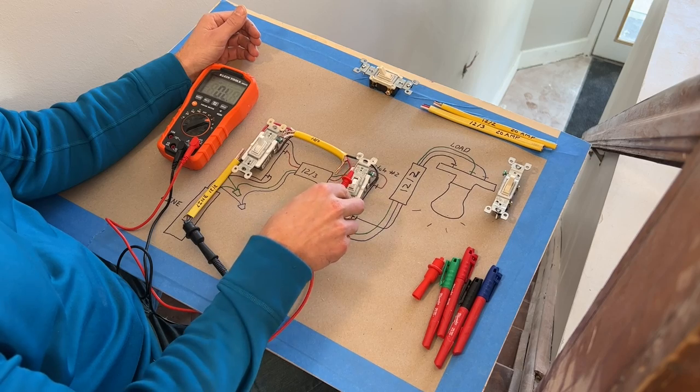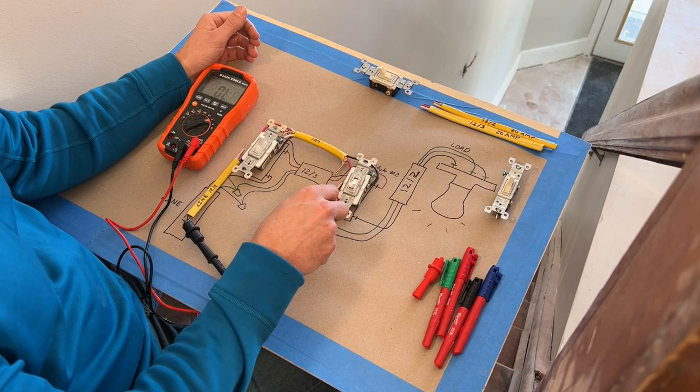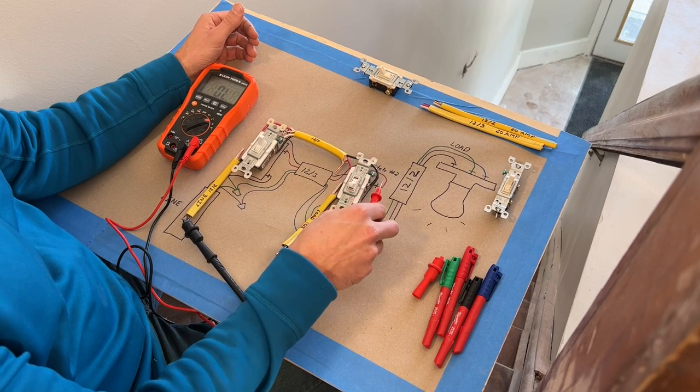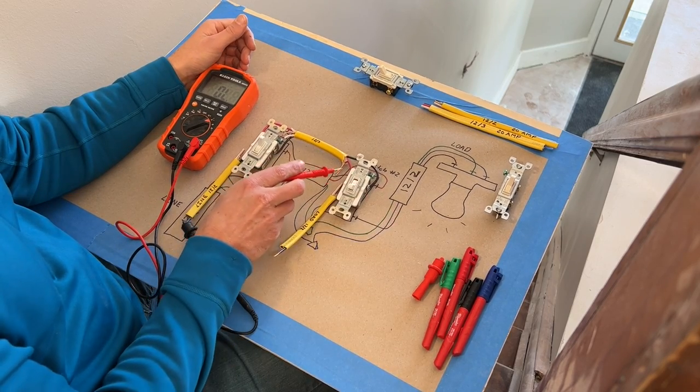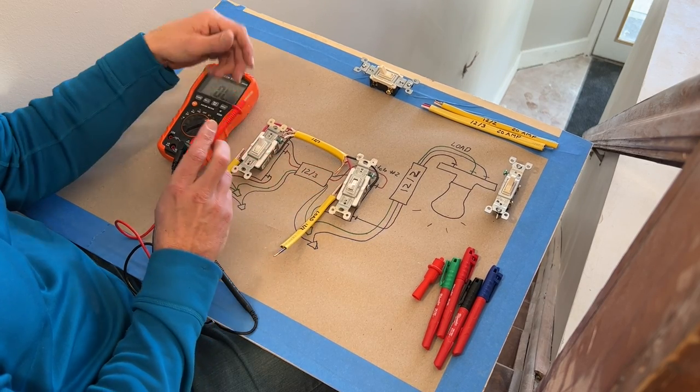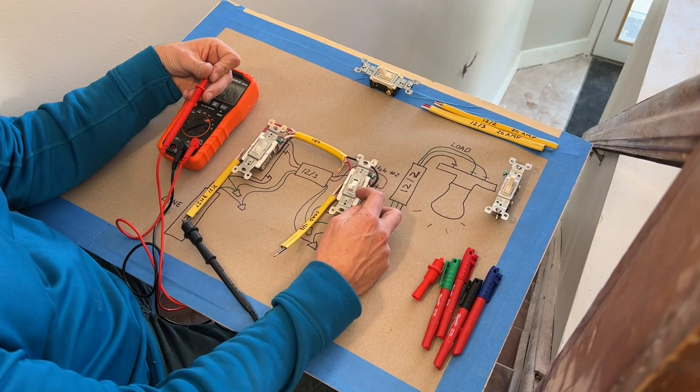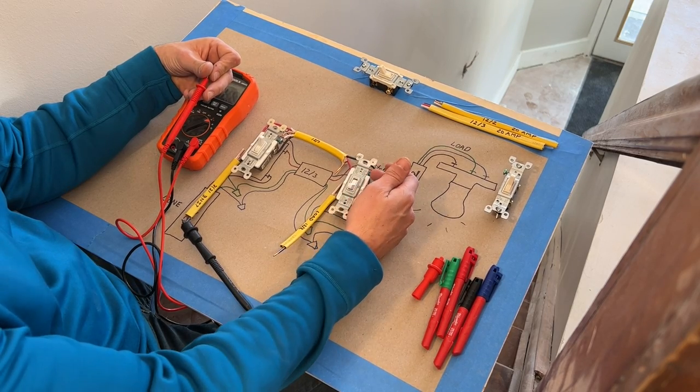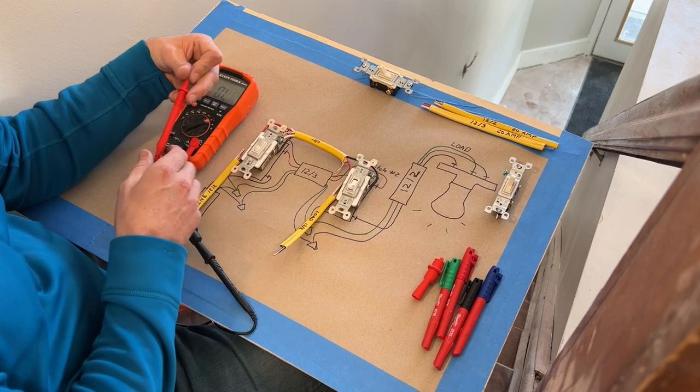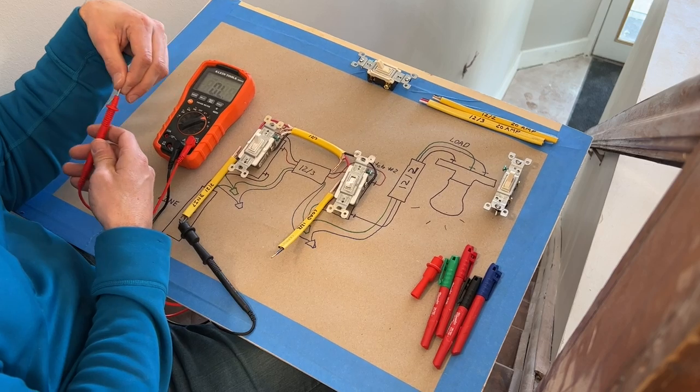So really, these switches are just flipping between connecting this black terminal to this gold terminal, or if you flip it the other way, it connects it to this gold terminal. So the travelers are critical to give you that connection between the two different light switches and the functionality where you're only using one light switch to turn on and off, or you turn it on at one light switch and off at the other. That's what the travelers are used for, and that's why they're critical to the correct functionality of a three-way light switch.